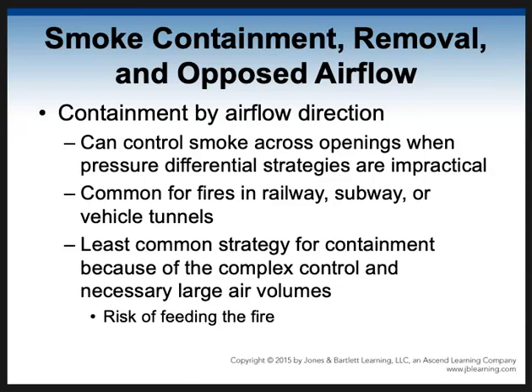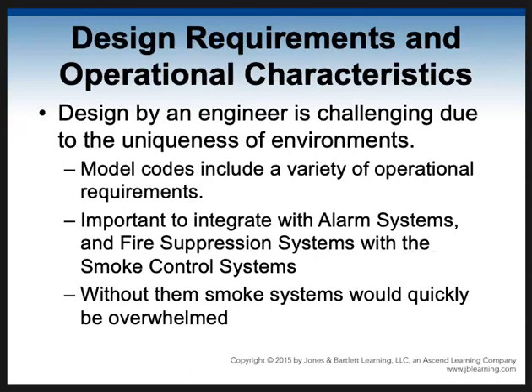But in railways, subways, big tunnels, imagine the channel has something of this nature. They can control smoke across openings when pressure differential strategies aren't going to work. So it's least common, but it's usually used in these places like subways. The problem is you're infusing a lot of air, so you risk feeding the fire.